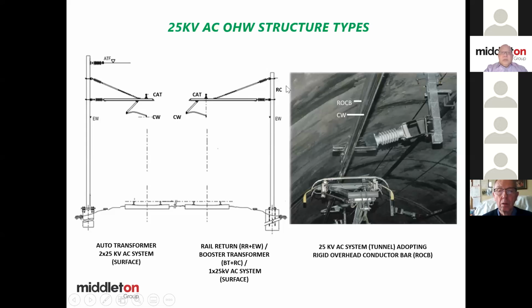the booster transformer will have a return conductor usually installed on the side here. These positions vary according to different installations. So just to give you a rough idea where they normally sit. Now for the auto transformer, the contact wire and catenary are the same, so in the same position. And you have an additional wire which is the auto transformer feeder. Sometimes it's called the negative feeder. The French have the negative feeder. The one I'm showing is 25 kV AC. So these two will be at plus 25 kV AC. And the earth wires are bonded to the running rail to carry return current.